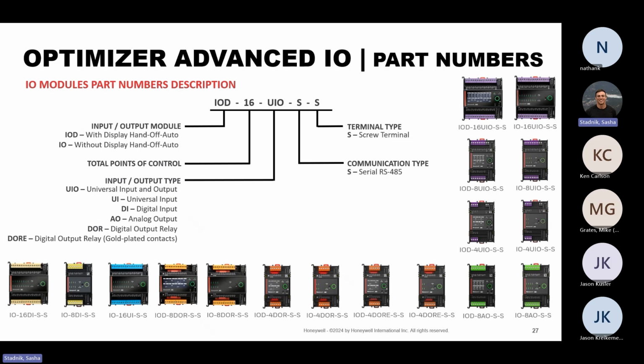So what's the difference between one having a display and the other not? The one with a display, like the UIOs, gives you a digital way to force inputs and outputs and configure the I/O module without needing the advanced controller or the Jace. As soon as I power this I/O module, I can start configuring every input and output without having a Jace, my laptop, or a supervisor there.